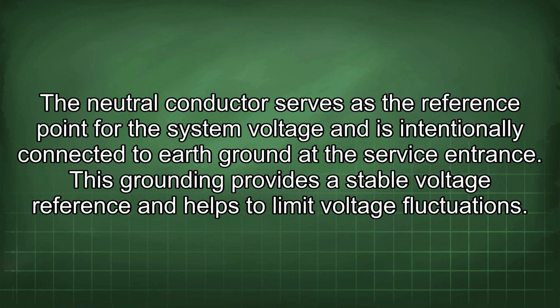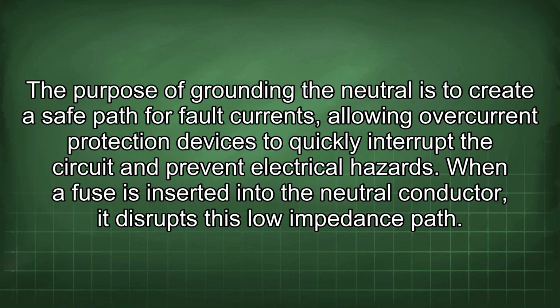The neutral conductor serves as the reference point for the system voltage and is intentionally connected to earth ground at the service entrance. This grounding provides a stable voltage reference and helps to limit voltage fluctuations. The purpose of grounding the neutral is to create a safe path for fault currents, allowing overcurrent protection devices to quickly interrupt the circuit and prevent electrical hazards.